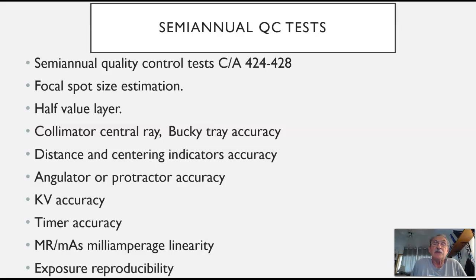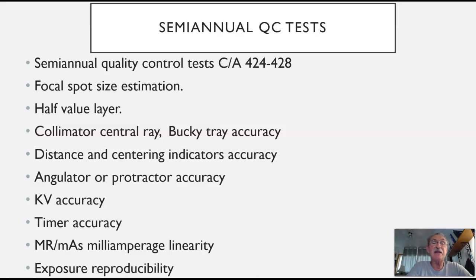Semi-annual quality control tests — a complete list is in Carlton and Adler on pages 424 through 428. Semi-annual tests include focal spot size estimation. We typically have two focal spots in clinical use, both a small and a large focal spot. Focal spot size estimation is not something technologists typically do — this is more for the quality control technologist or physicist on a semi-annual basis. The half value layer determines how much aluminum filtration is required to cut the intensity of the beam in half, giving us some sense of the output of our tube.